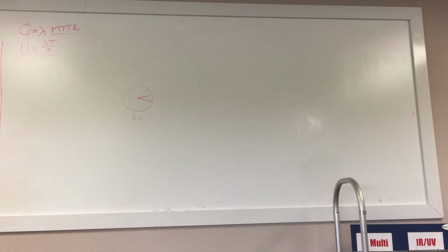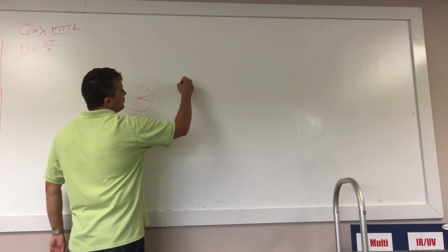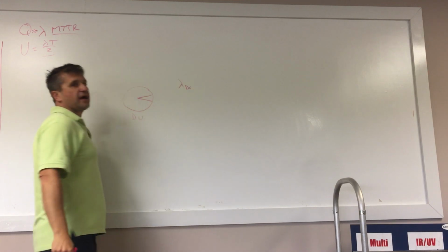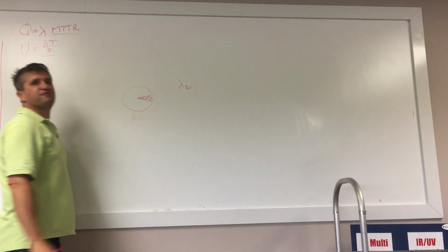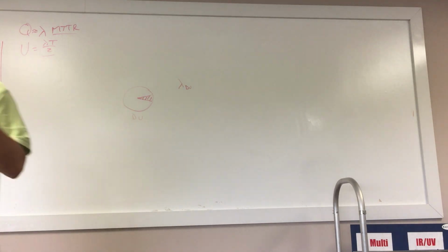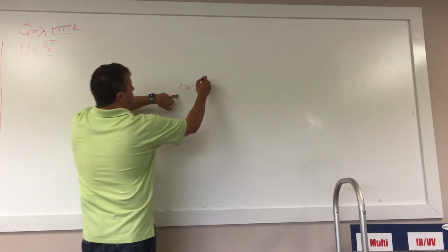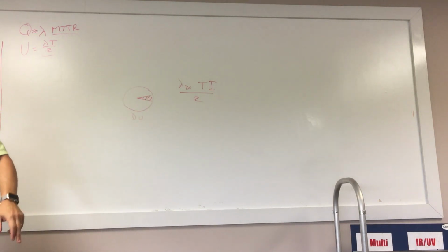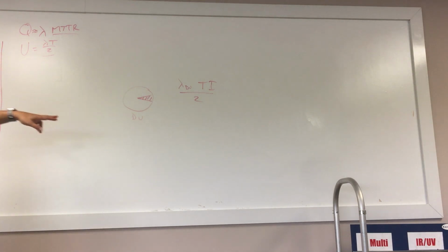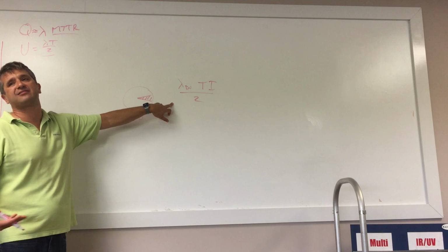If I were to be perfectly correct, my lambda du that I use here should remove these failures, but it doesn't, because not removing this little slice from the lambda du that we put into the unreliability equation is a conservative assumption that makes the math easier to do.